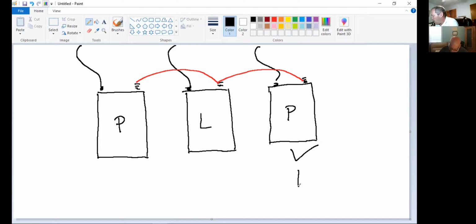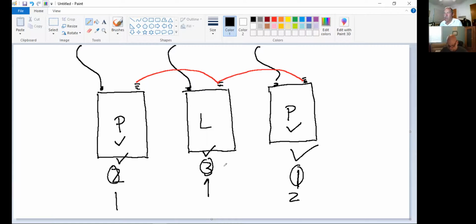So you said right power, left power, and then lighting. Okay, now it doesn't matter here, I could go 1, 2, 3, or I can go 1, 2, 3, as long as you're de-energizing both powers and then lighting last. Okay, lighting is always last for the same reason we did it on open delta. All right, you're dropping a little load, you're dropping a little load, and you're dropping the rest of the load. Okay, you're doing it in a step process.